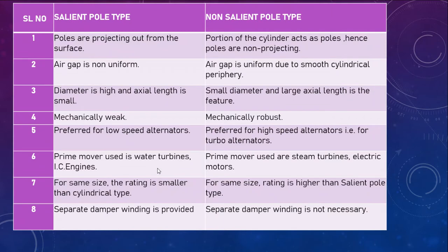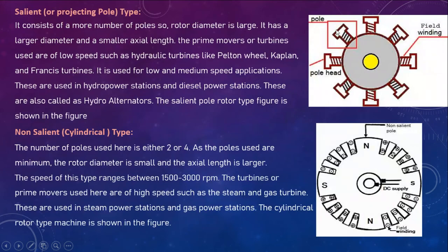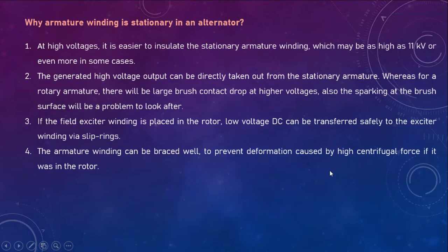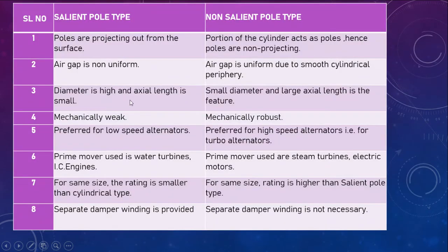Difference between salient and non-salient pole type rotors: in a salient pole, the poles are projecting out from the surface. In a non-salient pole, the poles are not projecting — the cylindrical portion acts as the poles, so poles are non-projecting. The air gap is non-uniform in salient pole type, while the air gap is uniform in non-salient pole due to its smooth cylindrical periphery. Salient poles have high diameter and small axial length, while non-salient poles have small diameter and large axial length.